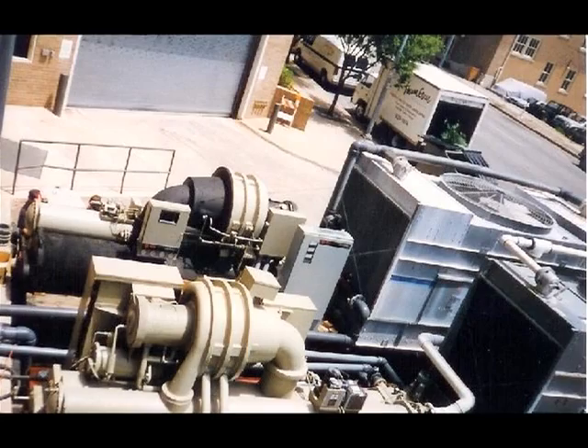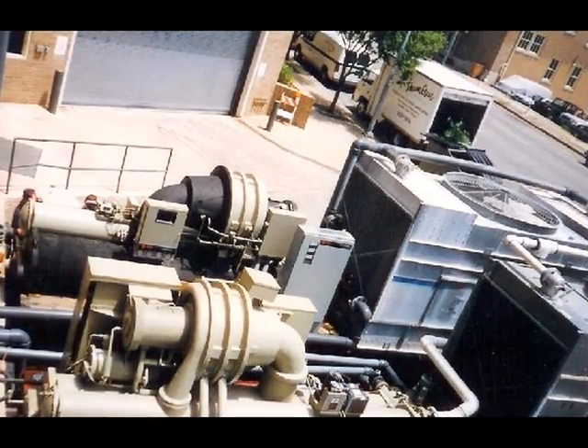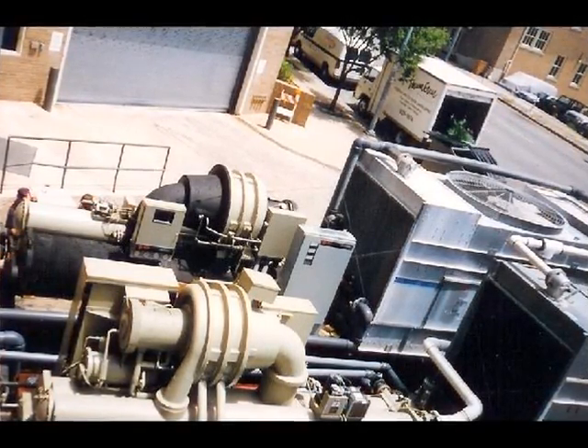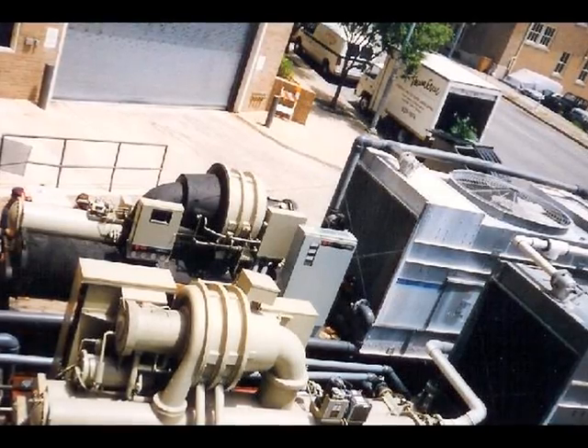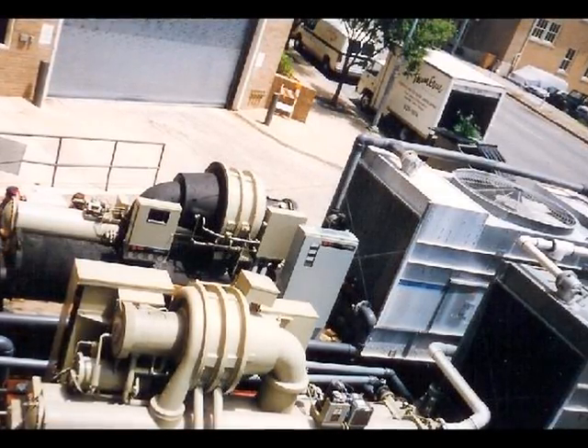If the chiller is suffering potential shutdown, the OAM can be installed, return that oil as fast as it migrates over to the evaporator, and the chiller will be running fine, regaining capacity, and saving a significant amount in energy costs. Many centrifugal chillers do not have an oil return system at all. Chillers without an oil return system invariably fall into the Scenario 3 category, regardless of load condition.